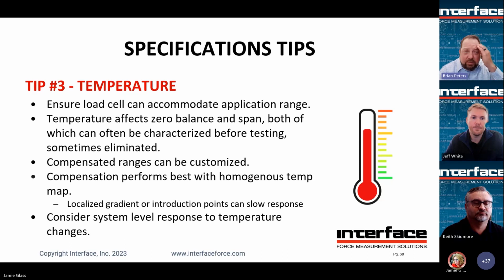Temperature. We've touched on this a few times. Key takeaways are to understand how it affects both zero and span. It's characterizable. You can probably compensate some of that out of your test or remove some of it. We want to make sure any temperature is as homogeneous or consistent as possible around that sensor. And then again, think about the rest of your system. If you can run your whole system up to temperature to see how it responds with no force, that would be ideal. Every mechanical thread and mechanical joint is going to respond differently to temperature. So even if you zoom in too much on the sensor, you may have other error influences that make the sensor almost irrelevant. Next one.